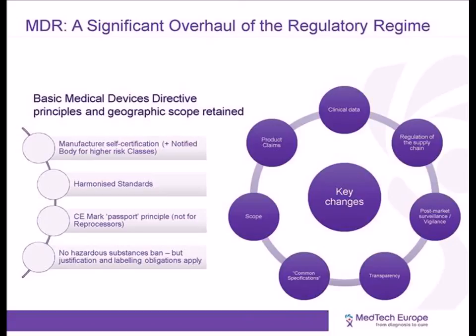The work needed to meet this expectation could certainly delay CE marking in some cases and add to costs, especially for those devices and manufacturers who have relied heavily on the equivalence route in the past. And there are also strengthened obligations for manufacturers to collect post-market clinical follow-up data according to planned post-market activities.